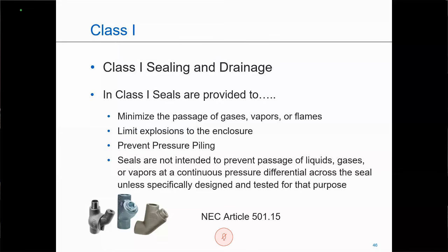In other words, when there's an explosion in the first enclosure, not all of the gas and vapors will explode right away. You're going to have that particular explosion start traveling through the conduit system, and the gas is going to compress, and it's going to pressure pile, compress into the next enclosure. And that enclosure then would have more gas in it than it was designed to handle, and that next explosion would actually be larger. So the sealing fitting is going to prevent pressure piling. Seals are not intended to prevent the passage of gases and vapors at a differential of pressure.